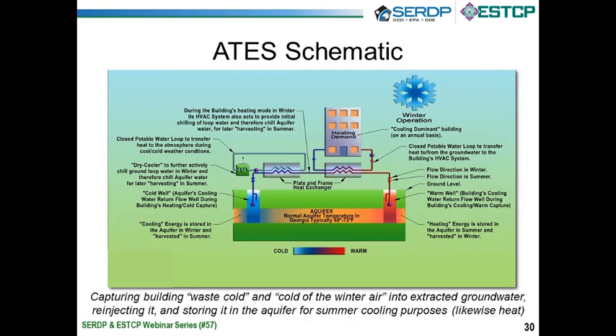So this is a schematic of the ATES system. At Fort Benning, we literally have four wells, but two will suffice for this discussion. Unlike BTES systems, when you get to big jobs with closed-loop systems, you're talking hundreds of holes. At Stockton College, they have in excess of 10,000 holes doing a whole campus. As you're doing heat conduction in and out of the formation, it takes a lot of boreholes, a lot of plastic pipe, a lot of grout. It's a very bulletproof system. It's closed loop, so you don't have to worry much about permitting or hydrogeological considerations.